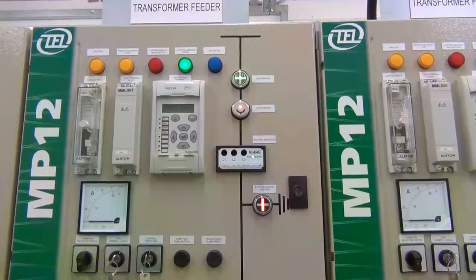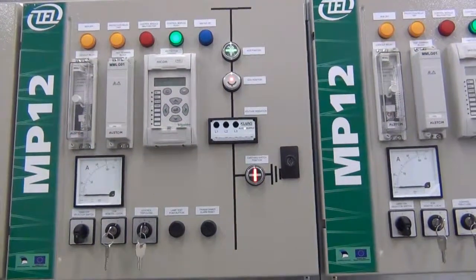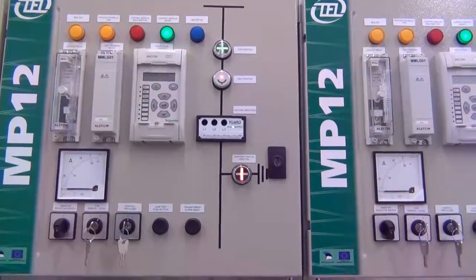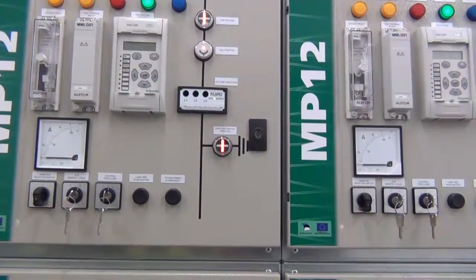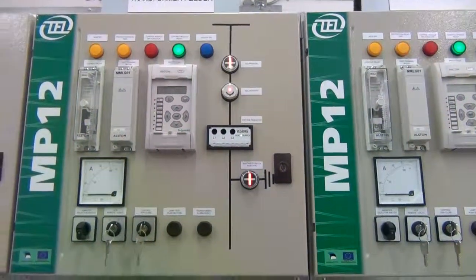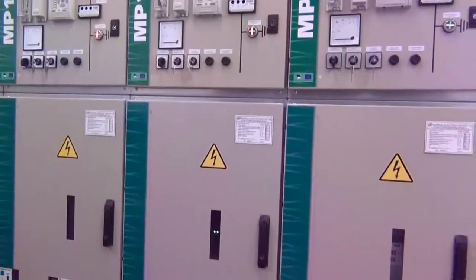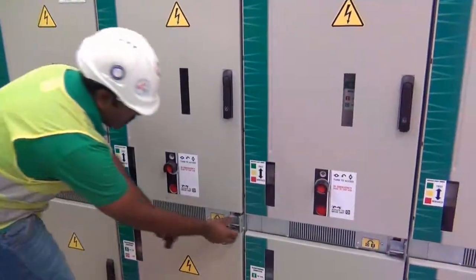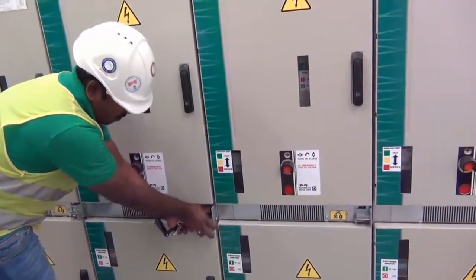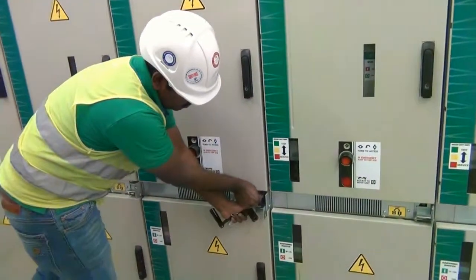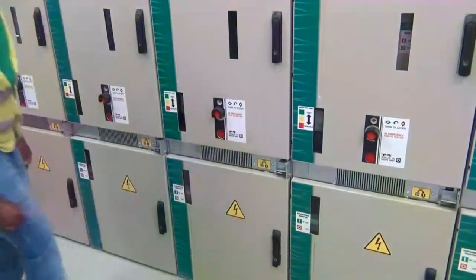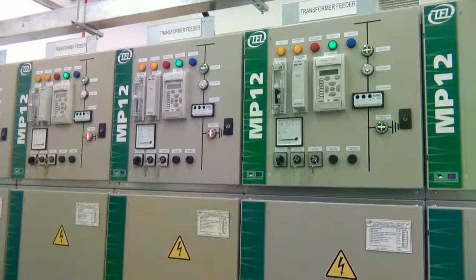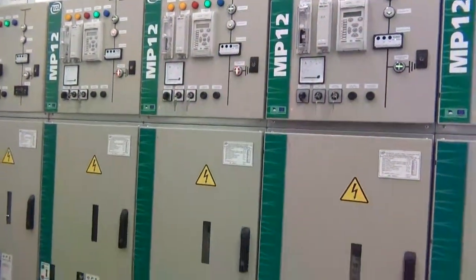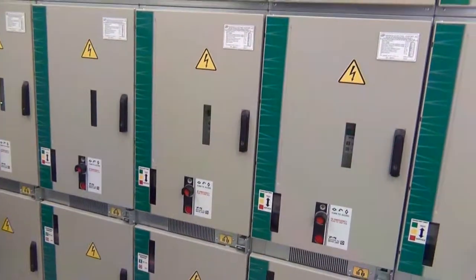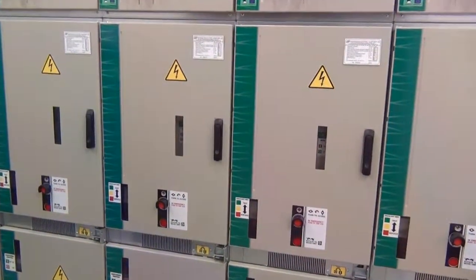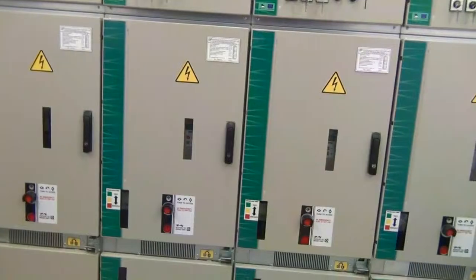The control module is ready to take open and close commands. Now we'll close the breaker. Now in this closed condition of the breaker, it should not be possible to put the earth switch on. You are not able to even get access to the earth switch compartment. Now we will get the trolley out. It is in test condition. We will now have to take the breaker out in the completely drawn-out condition.